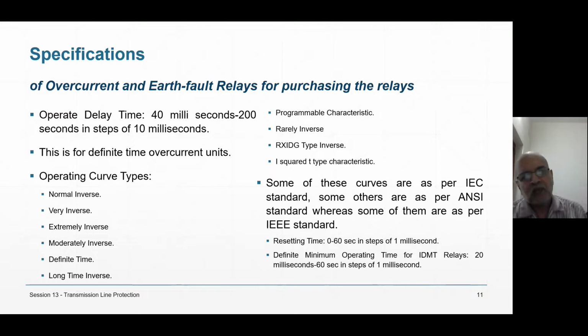Operate delay time. This is only for definite time overcurrent relay, 40 milliseconds to 200 seconds in steps of 10 milliseconds. This is only for definite time units. Operating current curve types. How many curve types is it giving you?